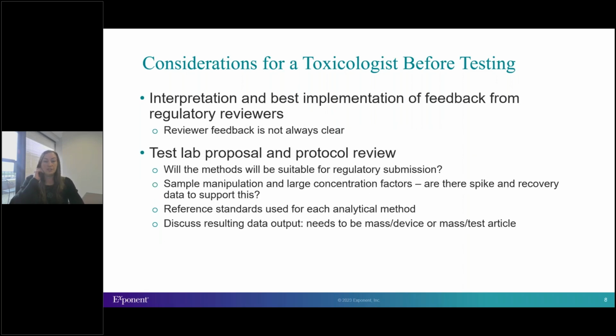Other considerations to think about before testing are interpretation and best implementation of feedback from regulatory reviewers. So it's not always clear from reviewer feedback how it may relate to your specific device. For example, I recently saw feedback requesting the standard 50 degrees Celsius extraction temperature, but for an externally communicating device that would never get near 50 degrees Celsius, used at ambient room temperatures.